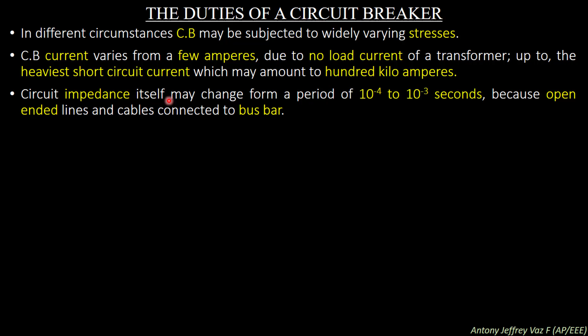Circuit impedance itself may change over a period of 10 power minus 4 to 10 power minus 3 seconds because of open-ended lines and cables connected to the bus bar. We know a lot of complex circuits are connected to the power system. These power systems have a lot of open-ended cables running for a long distance, but at the end of the line no device will be connected, or sometimes the device may be connected or left unconnected. Such long open-ended lines create impedance, which will change over a period of 10 power minus 4 to 10 power minus 3 seconds. This impedance has a huge impact on the power system, and when a short circuit or fault occurs, this impact is passed on to the circuit breaker duty.